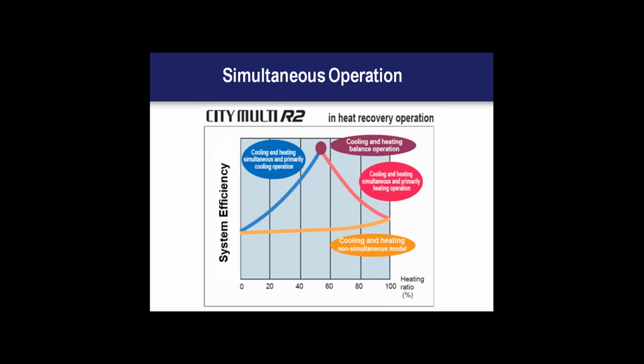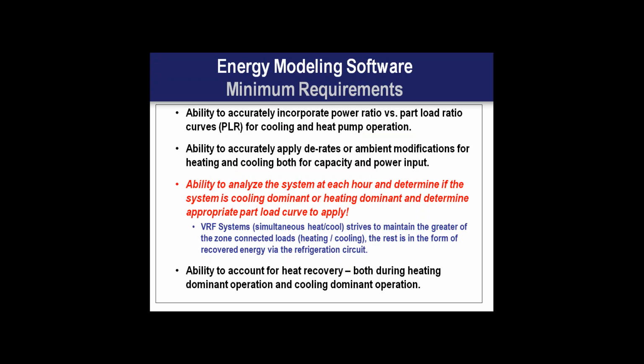Again, it's this 50-50 balance point, when you're in this recovery mode, where your system efficiency can really skyrocket. The problem is that most systems don't operate at this point all the time. In fact, the percentage of time they spend operating near that point is very dependent on building application and the grouping of zones. In these simultaneous heat recovery systems, we usually recommend grouping in an equal percentage ratio, internal with external, to harness that heat recovery potential and maximize those hours where you're approaching the highest system efficiency level. This is really where the need for energy analysis tools comes into play, because that is so dependent on the building profile, the specific project location, and how those zones are grouped.